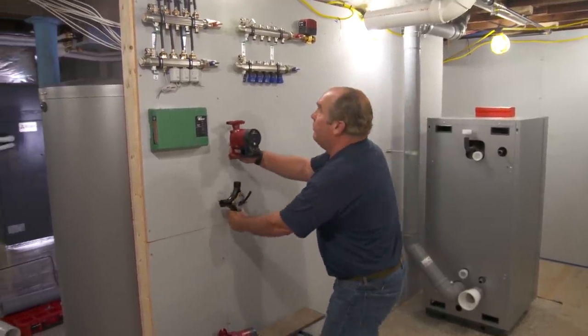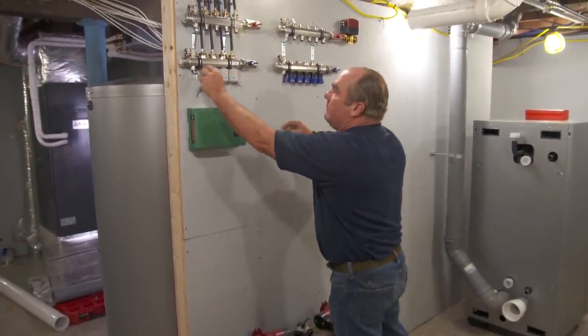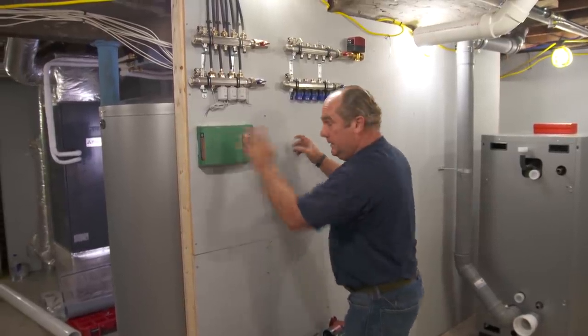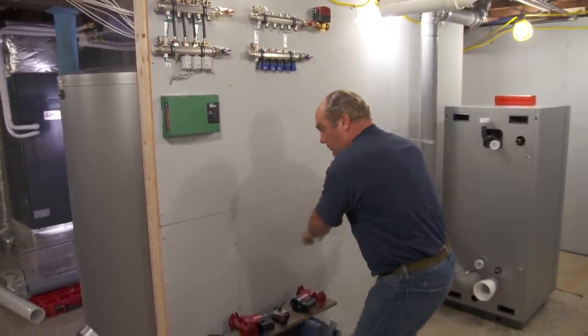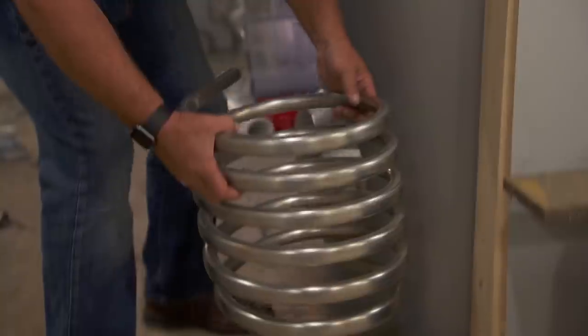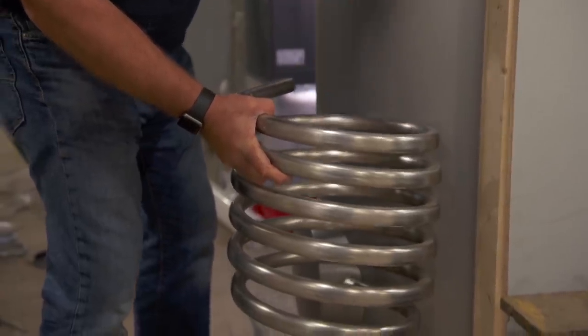We'll have another mixing valve and pump right here. Power heads on the manifold with local thermostats will wire down to this point. The last piece of hydronic piping is another circulator pump that feeds into a coil sitting inside a stainless steel tank to make hot water for the faucets.